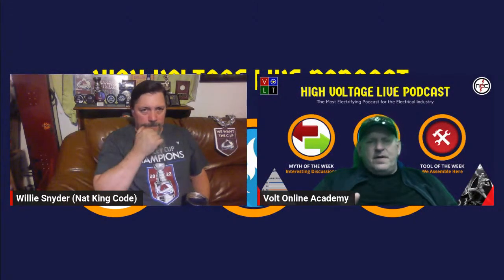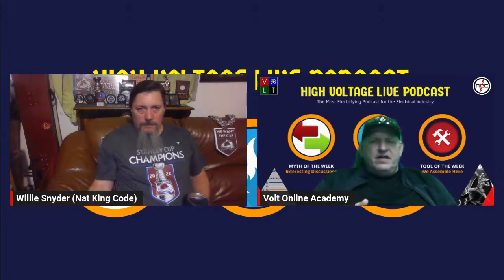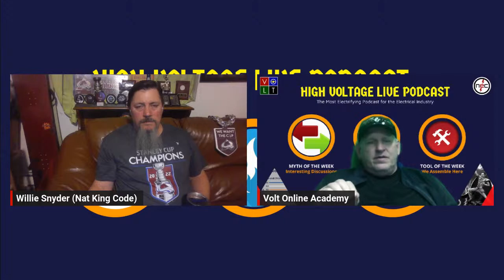I find this topic interesting because we're talking about using other NFPA standards with the NEC. I'm doing this with Article 110 as an example up at the front, with 110.16, 110.21, and 110.24. But what I probably want to do is a little series of this, going through the code showing the interaction, because there are other NFPA standards. Especially when we get into hazardous locations, I hadn't seen anybody do a podcast yet showing how to do classification, and that will take some time, because there's a lot of things we need to look at.